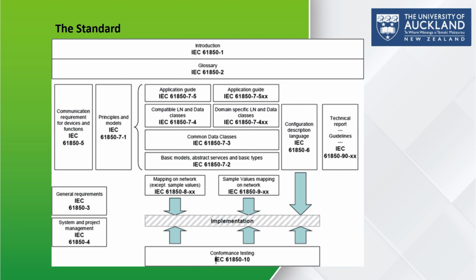The communication requirements for devices and functions are covered in IEC 61850-5, and the fundamental principles and the modeling approach are defined in IEC 61850-7-1. The core of the standard lies in the IEC 61850-7 series, which defines data models and logical nodes. These include basic models and abstract services, common data classes, and logical node classes.